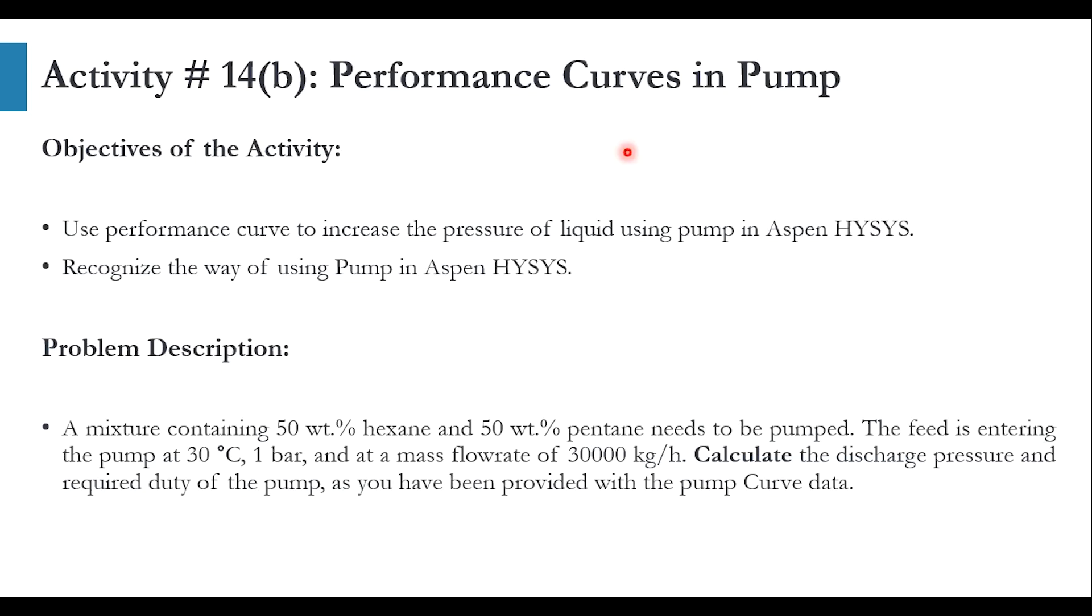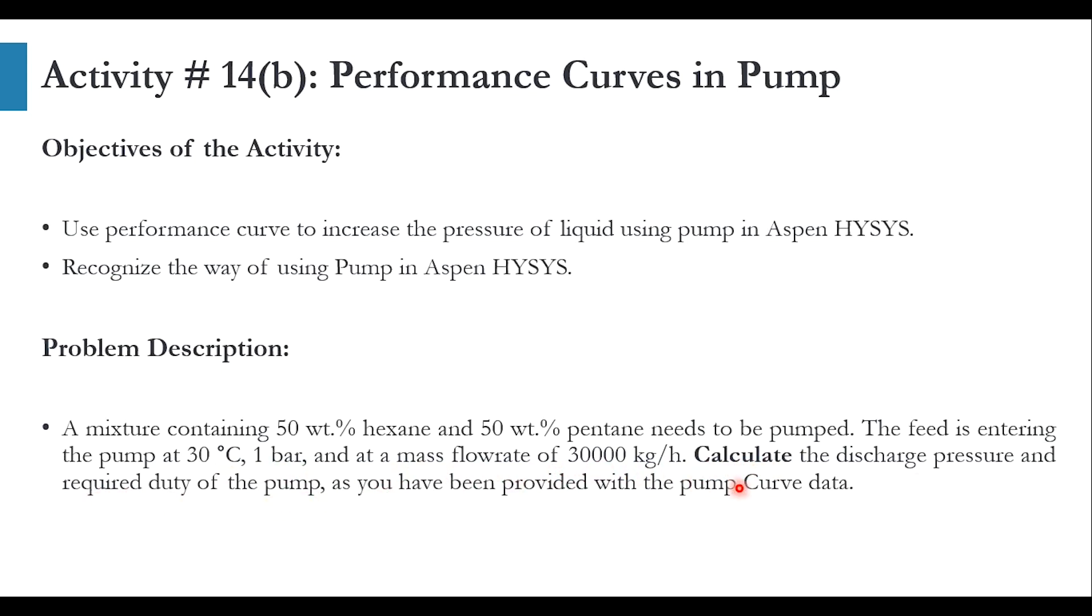The problem description is that a mixture which contains 50 weight percent hexane and 50 weight percent pentane needs to be pumped. The feed is entering the pump at 30 degrees Celsius, 1 bar, and at a mass flow rate of 30,000 kg per hour. Calculate the discharge pressure and required duty of the pump as you have been provided with the pump curve data. We have been given all the conditions of the feed stream like temperature, pressure, flow, and composition.